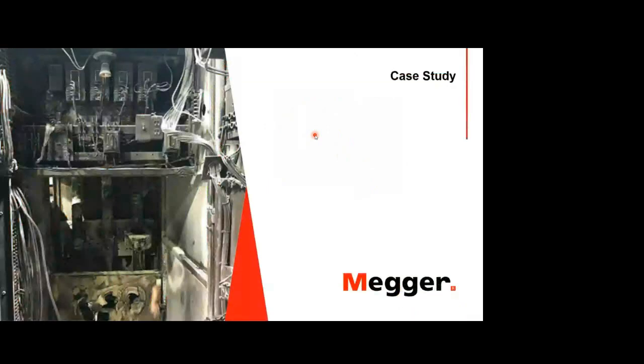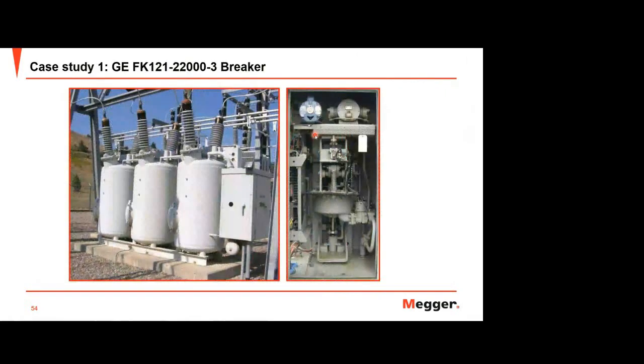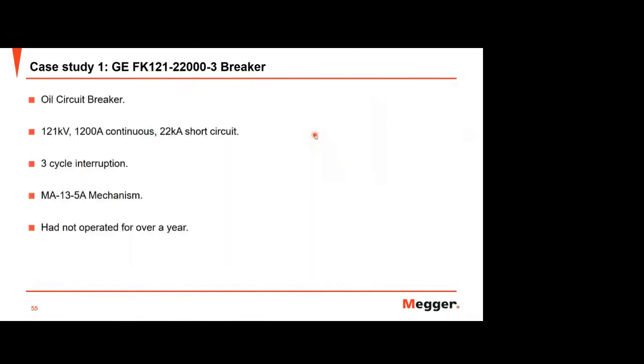Okay, then we continue to the case study. Maybe I will make it a little bit faster. This is one example case study that Megger has done before, used on the GE FK121 22,000 breaker. It's an oil circuit breaker with 121 kV, 1200 amp continuous current and 22 kA short circuit. This is the spec of the breaker, which had not operated for over a year.